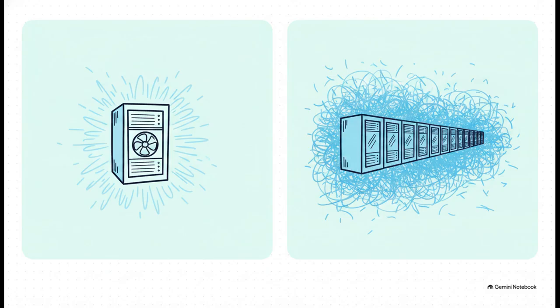But what happens when you need to scale beyond a single rack to an entire row of servers? The building block methodology scales up the cooling right along with it. You have options like the liquid-to-air sidecar CDU, which gives you up to 200 kilowatts. But check out the in-row CDU option, which scales all the way up to an incredible 1.8 megawatts of cooling capacity for the row. To put that into perspective, that is exponential scaling. It ensures that as you multiply your compute blocks, your cooling blocks grow right alongside them to handle that staggering thermal load.